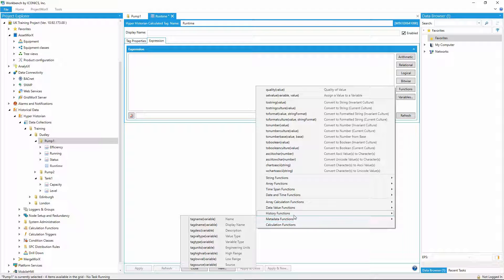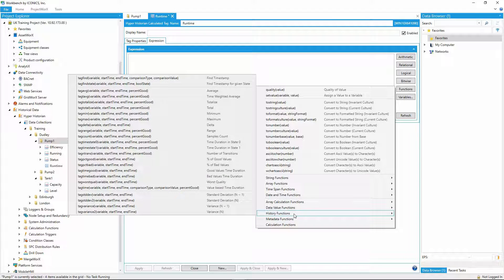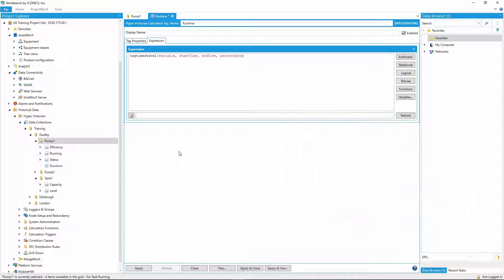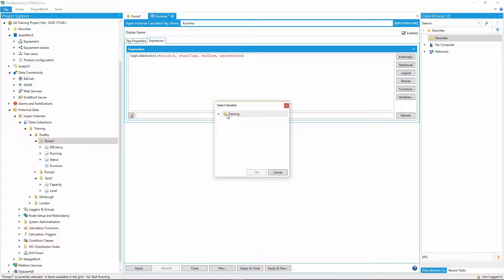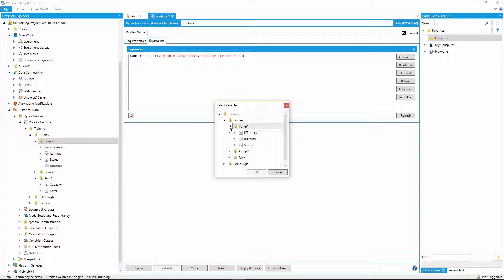I'm looking for the time that the running signal has been set to true, so I'll select the tag time state 1 function, which allows me to specify a data signal, a start time, and an end time for the calculation, and the percentage of good quality samples I need for this calculation to return a value.